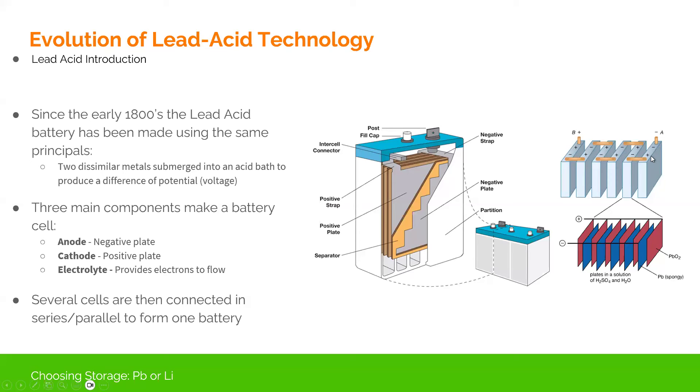A 12-volt battery has six 2-volt cells in series. A 2-volt battery simply represents one cell. In the flooded lead acid range, you can find a variety of styles: 2-volt, 4-volt, 6-volt, 8-volt, and 12-volt. Typically you then bring batteries externally together through busing to create a higher voltage than 12. The 12-volt configuration really reigns when it comes to flooded lead acid or AGM batteries.